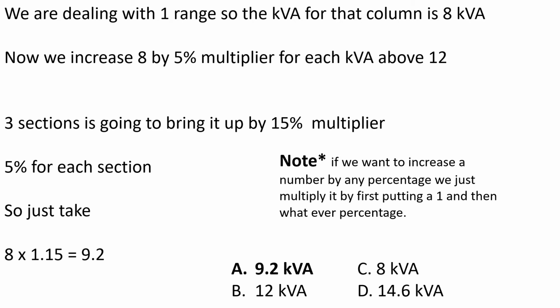I want to note that if you want to increase any number by a percentage, we will just multiply it first by putting a 1 in front of it and then whatever the percentage is. In this case, we want to increase it by 15%. So we just take 8 multiplied by 1.15, and that is going to give us 9.2 kVA.